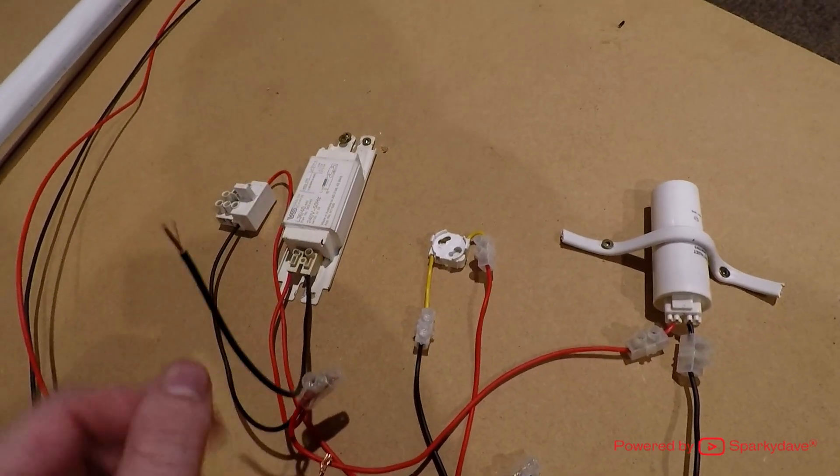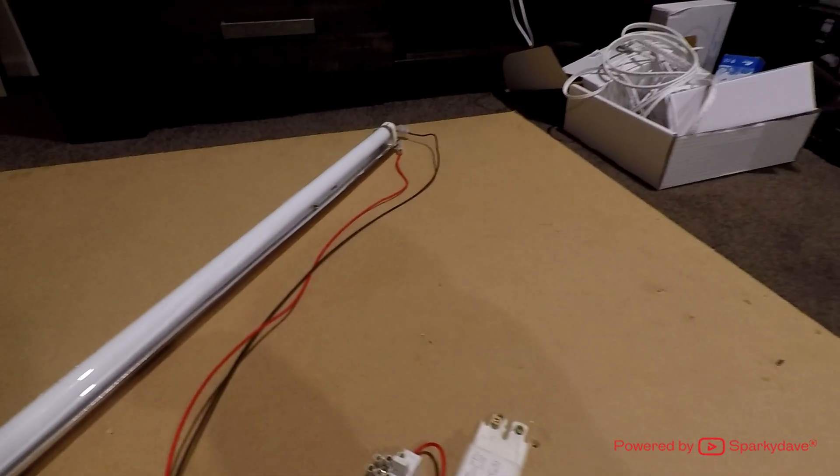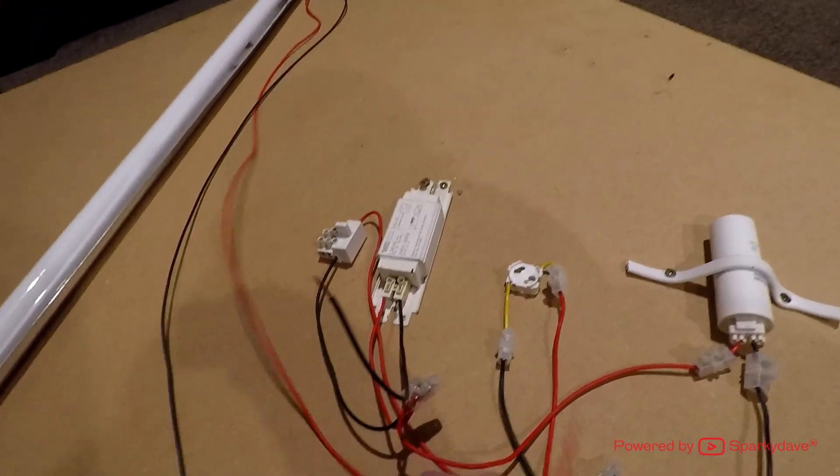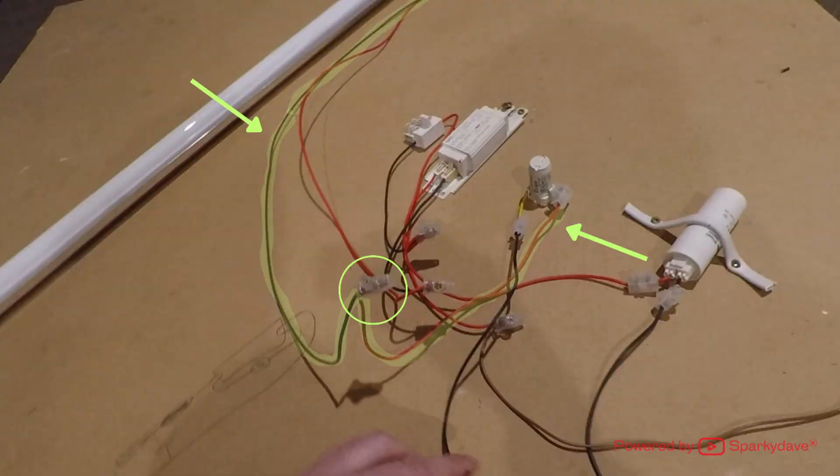From the black side of the ballast I'm going to go to one end of the light fitting itself on the red cable. On the black cable of that same end I'm going to connect it to the red side of the starter.